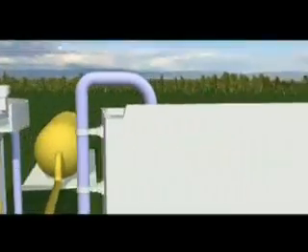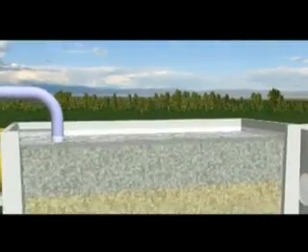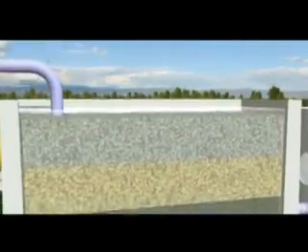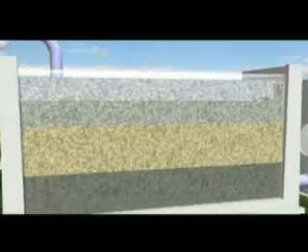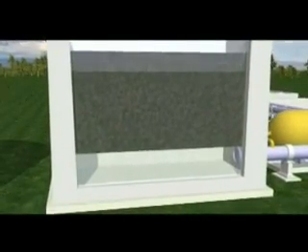The water now needs filtration to get rid of any remaining particles. Water is filtered slowly through very fine sand or sand-like material. For some river waters, we use ozone gas injection as a treatment stage. This can work in conjunction with GAC or granular activated carbon treatment, where the water is filtered through carbon granules to take out any undesirable traces of largely natural organic materials. The carbon in these filters is removed and regenerated by heat so it can be used again.